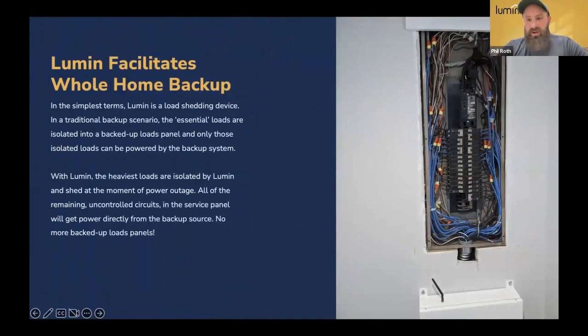I created this to give a really basic idea of what we're doing, because I think it's easy as an installer to get locked into the idea of isolating the loads you want to back up, separating them from the main service panel, and only backing those up. What Lumin attempts to do is flip that thinking: instead of isolating essential loads, you isolate any loads that might threaten your battery-based inverter.